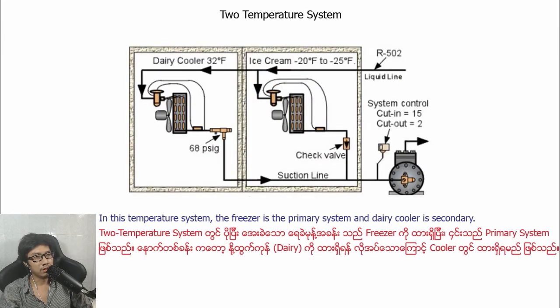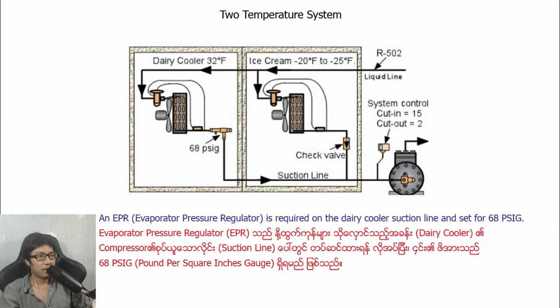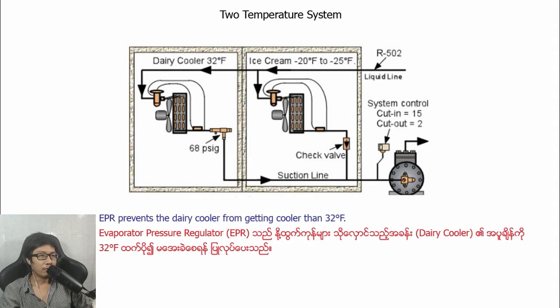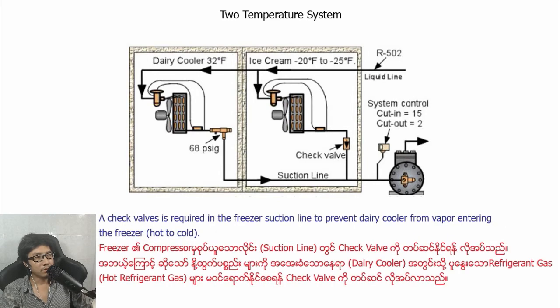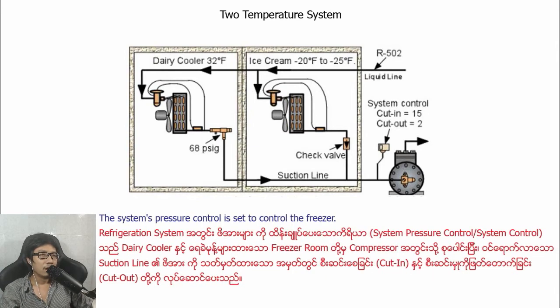Two temperature system. In this two temperature system, the freezer is the primary system and the dairy cooler is secondary. An EPR, evaporator pressure regulator, is required on the dairy cooler suction line and set for 68 psig. The EPR prevents the dairy cooler from getting cooler than 32 degrees Fahrenheit. A check valve is required in the freezer suction line to prevent vapor from the dairy cooler from entering the freezer. The system pressure control is set to control the freezer.